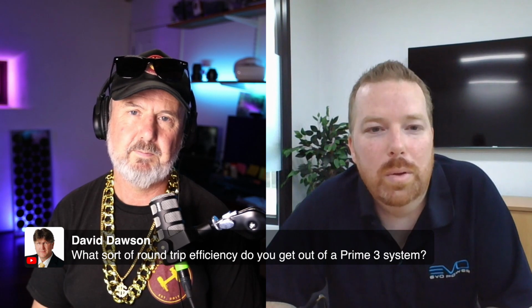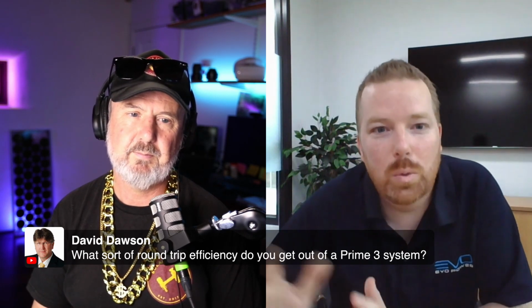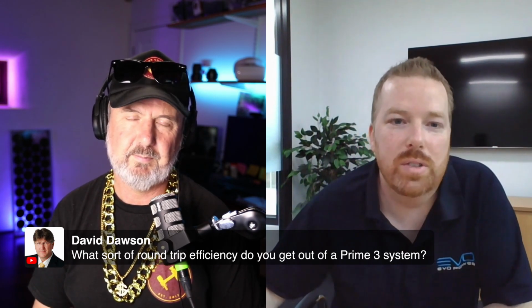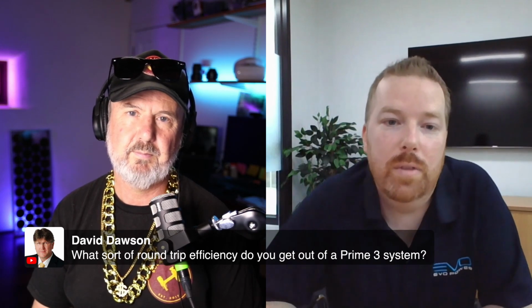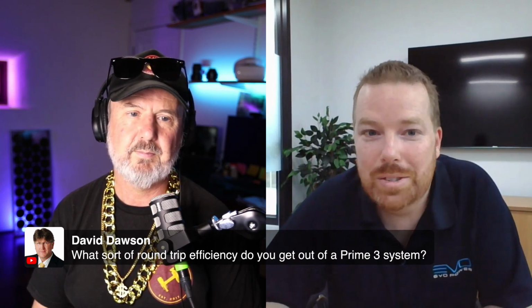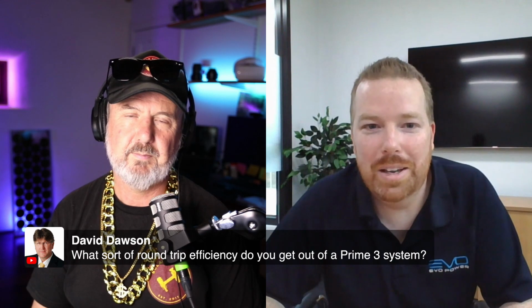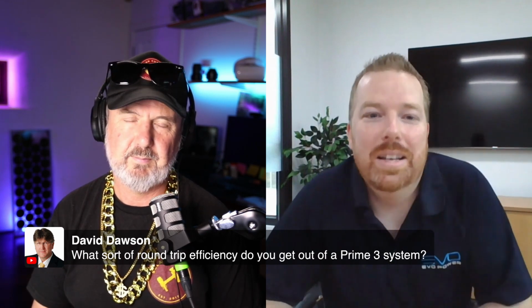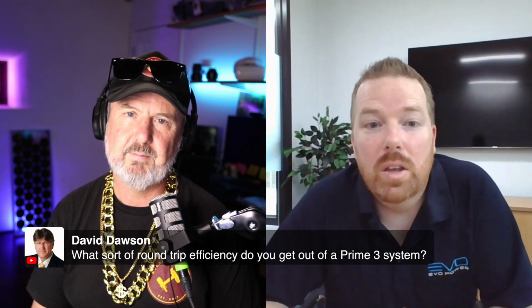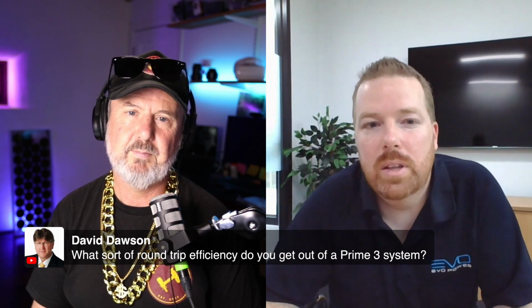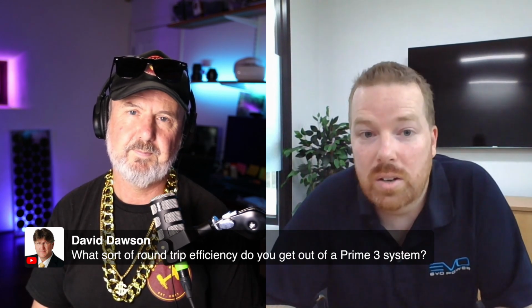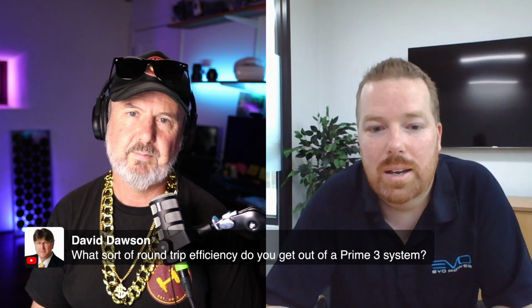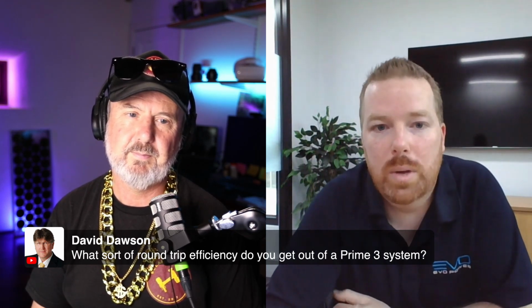If you remember the Powerwall 1 and the original Resu batteries, they were all running off the nominal value, kind of like lead acid batteries too. It's 100 amp hours, 12 volts, but you can only actually access 50% of that typically. So in the earlier days they were running off that. They've just recently made a change at LG, saying it's the full 100% usable energy.